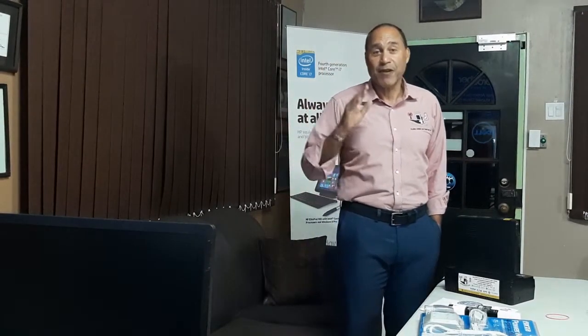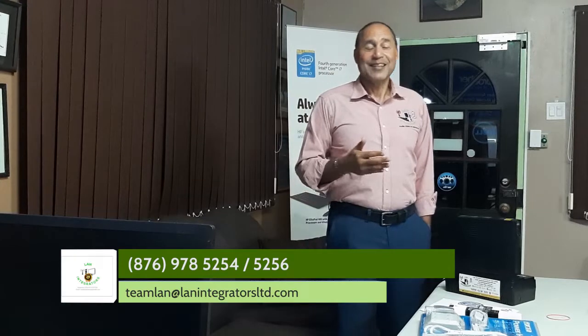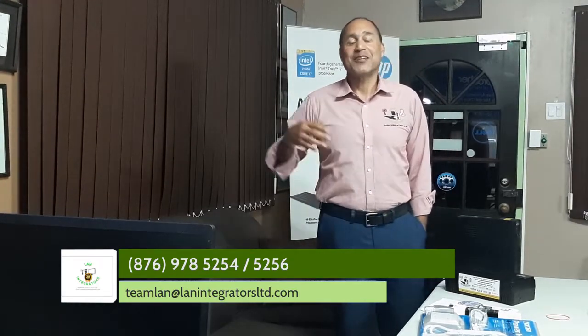For our critical loads now, and data centers, and areas where you are going to need protection for very high-end equipment, you put in what is known as a true double conversion online UPS. And basically, that's a UPS that pretty much runs all the time on the battery. And you get a clean sine wave coming through all the time. You have no distortions, and what your power provider does is just charge your batteries. Power coming in is converted, it's then used to charge the battery. Power going out is then converted again to AC and goes to your equipment. That's why it's known as double conversion.